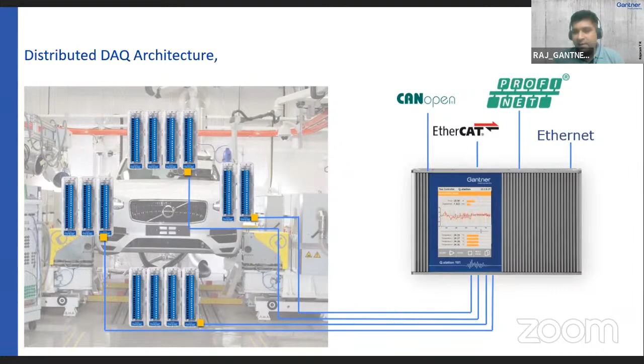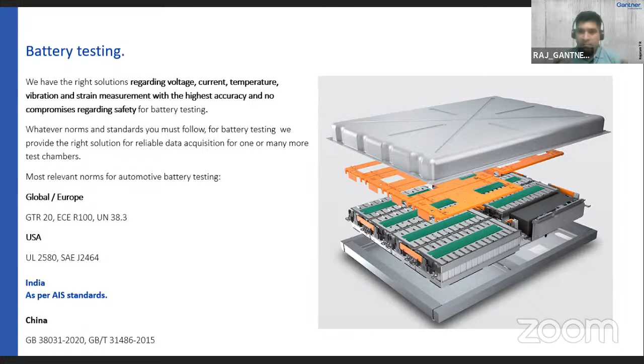Now, because of the lack of time, I will not go into detail on various testing of battery, inverter, etc. I will concentrate only on battery testing today. When you test a battery, what are all the parameters you are going to measure? You are going to measure voltage, current, temperature, vibration, and strain. We have modules which can measure these parameters at the highest accuracy, with a resolution of 24 bits and a sampling of 100 kilohertz, whatever testing standard you follow. You have different testing standards in different countries. In India, as per the AIS standards, our modules can meet the requirements specified in these standards.